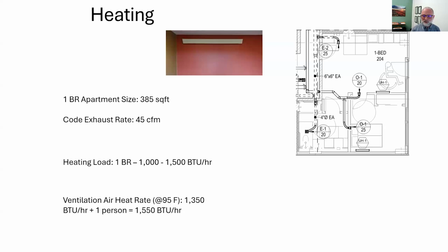By code, the apartment only requires 30 CFM of ventilation air because we are continuously exhausting the kitchen and the bathroom. We require 45 CFM of continuous exhaust. To balance the exhaust, we're providing 45 CFM of air to the apartment. If we heat that ventilation air to 95 degrees, it provides 1,350 BTUs per hour of heat to the space. Taking credit for one occupant, we've met the peak load just by providing heat to the ventilation air.